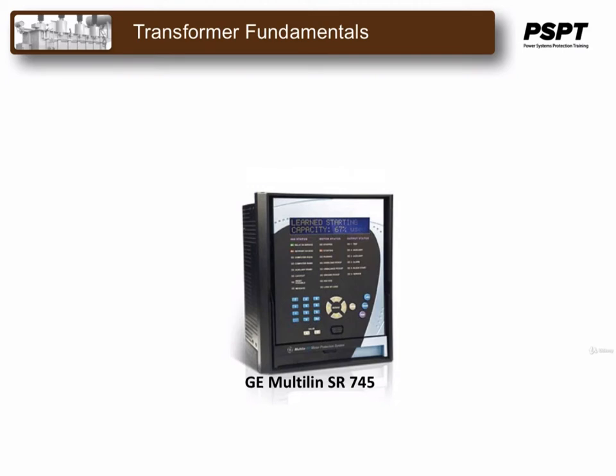Multiple current and voltage inputs are used to provide primary protection, control, and backup protection of transformers, including current differential, restricted ground fault neutral, ground overcurrent, overfluxing, and on-load tap changer compensation. The 745 also includes analog inputs and outputs, while incorporating advanced features such as transformer loss of life monitoring.